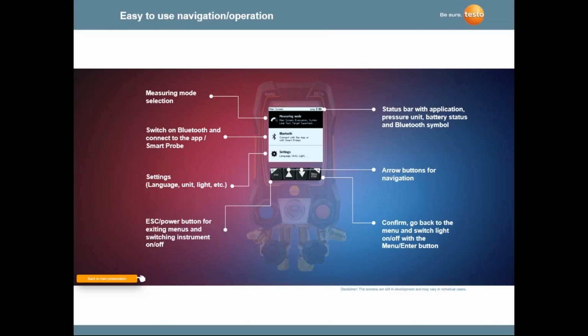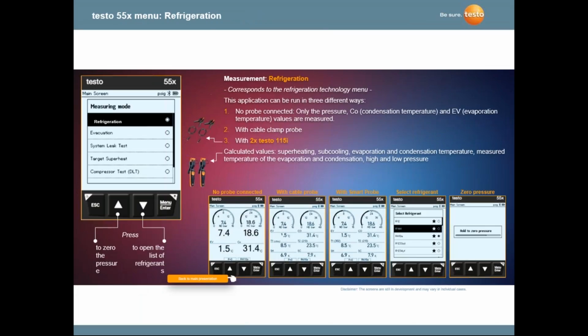Navigation of the instrument, you'll see the display itself. There's a measurement mode. If I select that measurement mode, I go into a lot of different modes of tests that I can do. I can do superheat subcooling calculations, evacuation, vacuum test, a pressure leak test, targeted superheat test, compressor test, as well as delta T's.